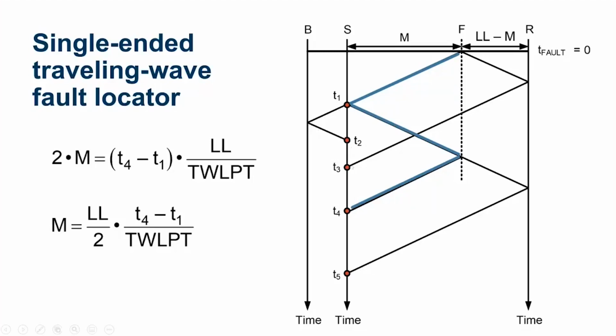The other thing you see here is time T3. This is the reflection of the other traveling wave. So we've got a fault, where the wave was first launched from the fault, went to terminal R, and then it reflected from terminal R to the fault point. What we really would see is some reflection here and some of it passing through. So this is the pass-through of that first wave to point T3. Now what the guys in R&D have done is created a high-tech algorithm that's able to discern that this is the first traveling wave and this is the second reflection, and it ignores these two.